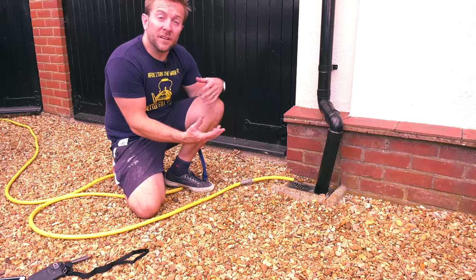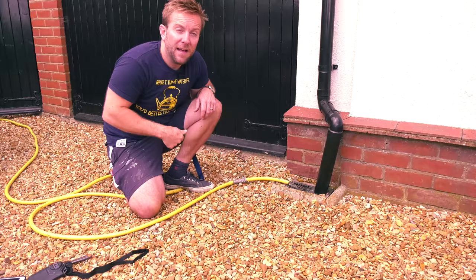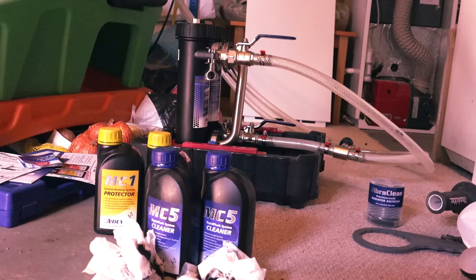What we're effectively doing now is pushing cold water down from our F&E tank. It can't go anywhere else apart from that one radiator at the end, and then it comes all the way back through into our manifold and out of the hose pipe, so we know we're flushing out any chemicals we've been using. Once you've done that, you're ready to shut off the drain, open all your radiators back up to normal system, and then move on to the stage of removing our MagnaClean, dosing the system, and leaving it in full working order.